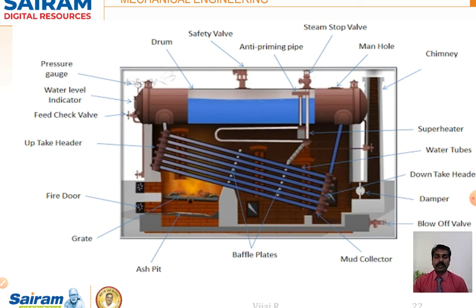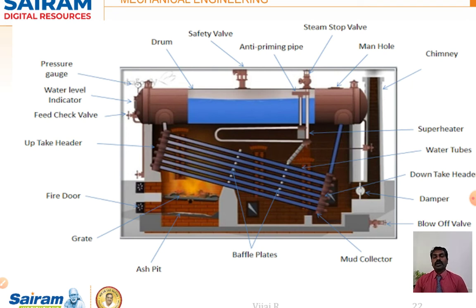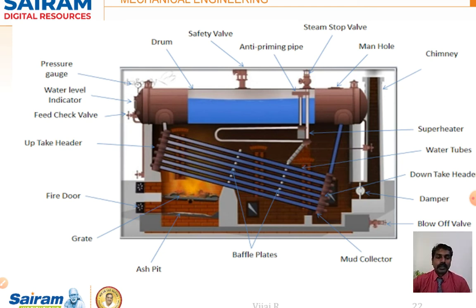Water from the drum goes down to the downtake header and fills into the tubes. At the bottom, coal is fired on a grate where fuel is burned. Hot flue gases spread across the entire area and pass over the tubes. Baffle plates direct the flue gas in a zigzag path to ensure contact with every tube, and the gases then travel to the chimney visible at the right end.